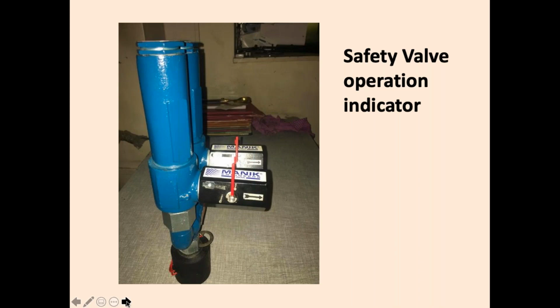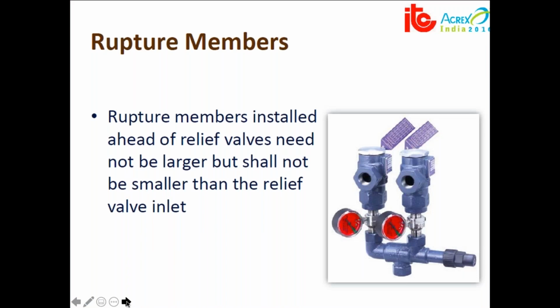There is a problem: you do not know whether the safety valve has operated or not. So there are indicators now available. If the safety valve blows off, the indicator will go to the right hand side, indicating that this safety valve is operated. These are available in India also now. Or people provide these rupture discs. These rupture discs are also important. Many people provide that with a pressure gauge. So if the safety valve is blown off, the pressure on that line will always be high because it will be discharge pressure. And then you will know that this safety valve is blown off, and then you can put the second safety valve into operation.